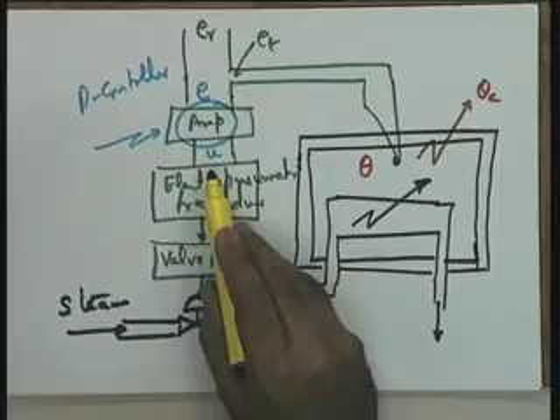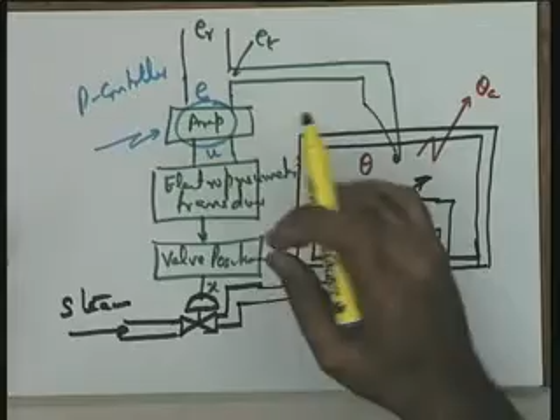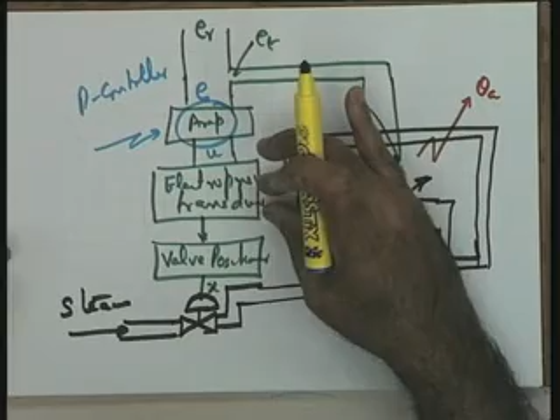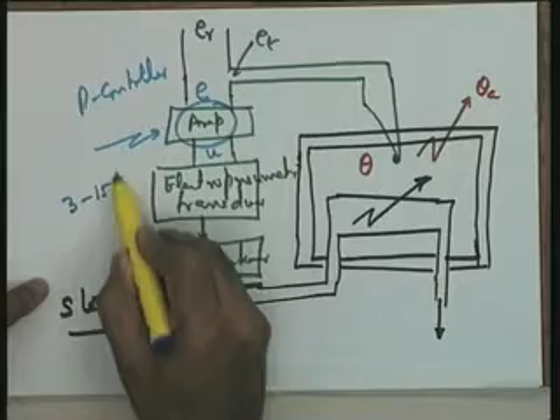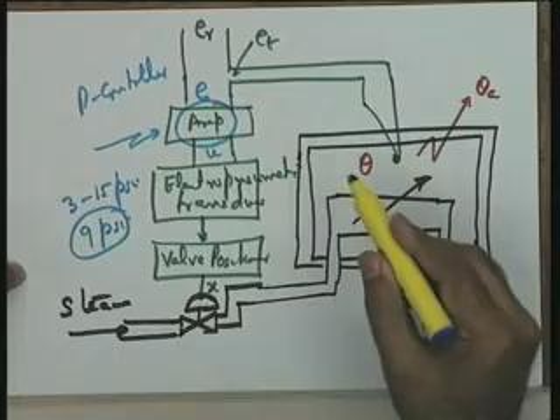Now please note, to maintain theta at theta r, you will require the heat exchange. So when this U is equal to 0, how do you get this heat exchange, please? This heat exchange you get by steady state or equilibrium setting of the valve positioner and the electro-pneumatic transducer. Recall that the electro-pneumatic transducer has a variation of 3 to 15 psi. Suppose the hardware adjustment in the electro-pneumatic transducer is done to, let us say, a value 9 psi, just a tentative value I am taking, and this pressure opens this particular valve the just amount which maintains theta at theta r when the equilibrium state is there. So, it means under the equilibrium state, the error signal is 0, the control signal is 0, and the prior setting of the electro-pneumatic transducer and the valve positioner maintains the heat balance.